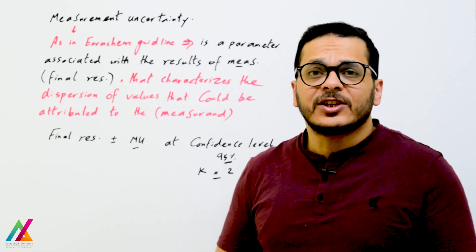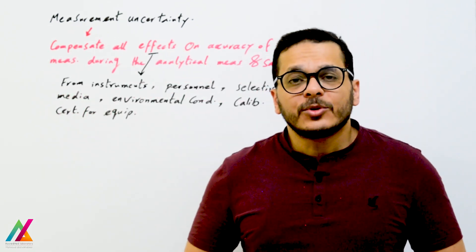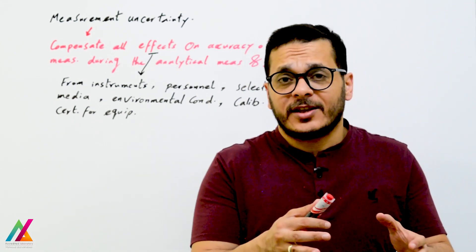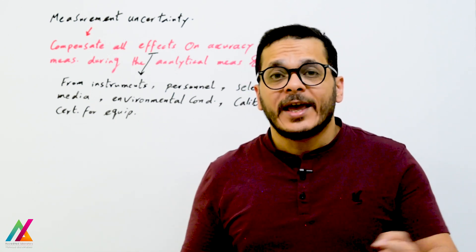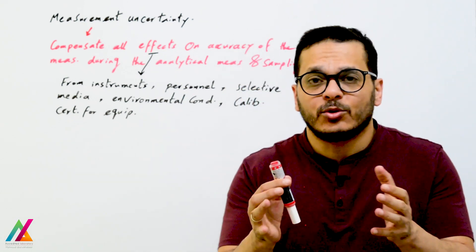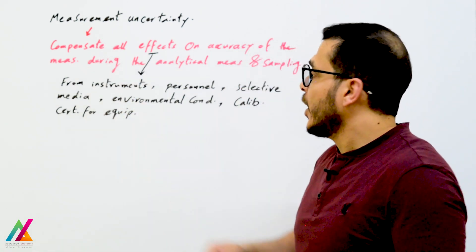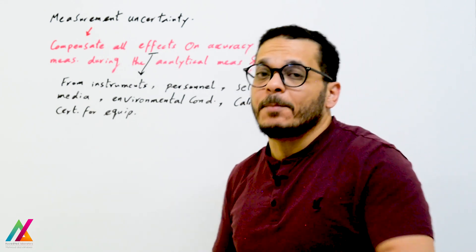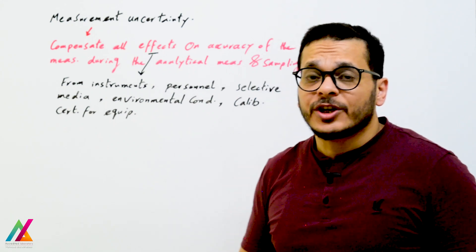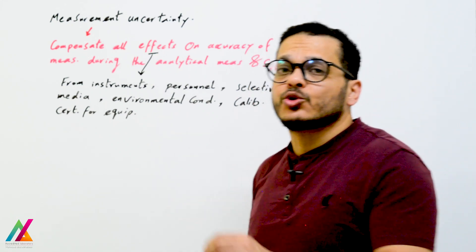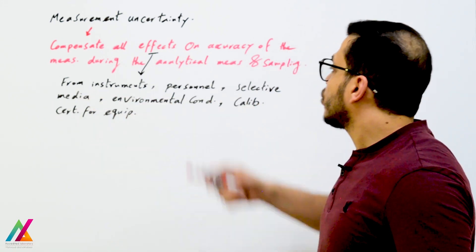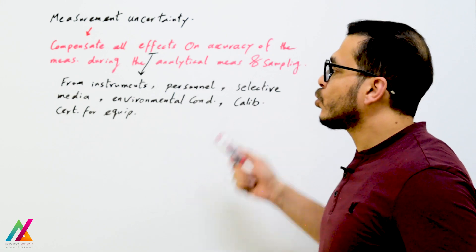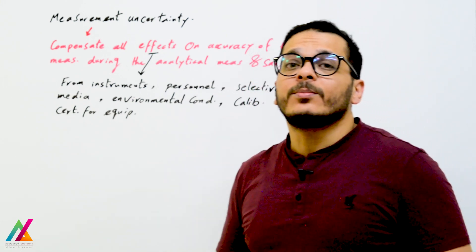This is reported at a high confidence level, most commonly 95%, at a coverage factor of 2. To calculate measurement uncertainty, you should first identify all sources that may affect the result of the analyte during the whole measurement process — from sampling up to analysis. These effects can come from biological, instrumental, and personal bias, selective media, environmental conditions, and calibration certificates for externally calibrated equipment.